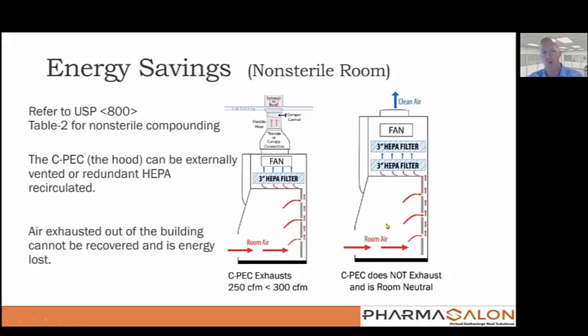Now, we still have to use what's called a low wall exhaust grill to create the negative pressure in the space, right? But understand that, let's say your business is at a point where you've got 4, 5, 6 of these powder hoods. The more you start connecting these things, the more you've got a domino effect of varying static pressures, which will make the room jump all over the place, but also that's more energy going out of the building. So my recommendation is that we use the low wall exhaust. I'm sorry, I don't have that picture, but we want to use the low wall exhaust to create the negative pressure for the CSEC and let the CPEC be independent of itself.